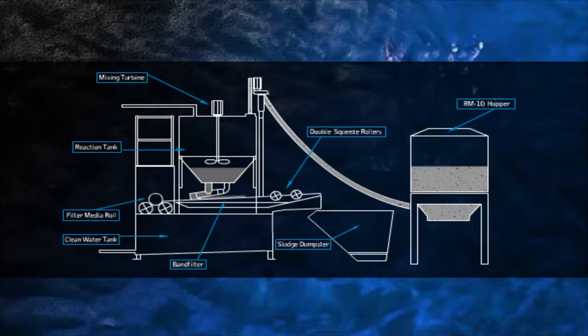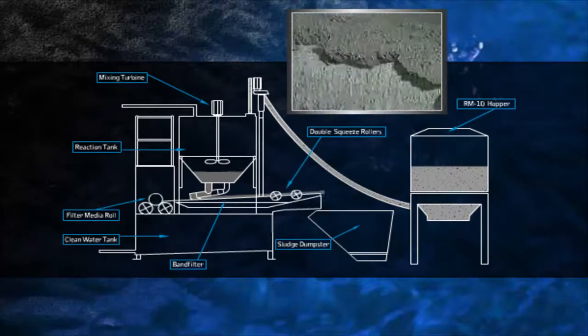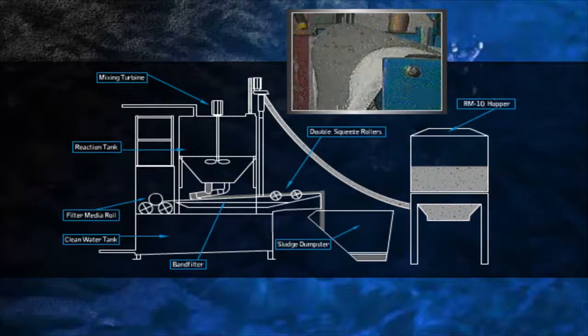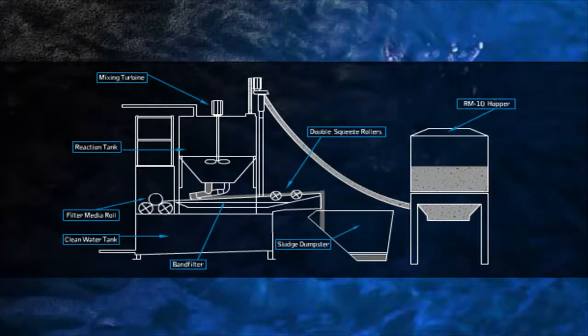The sludge falls onto the filter media where it de-waters by gravity to approximately 25% solids. The solids-laden filter media then passes under rollers that squeeze out any excess water. Both the solids and the filter media fall into the sludge hopper and are disposed of.